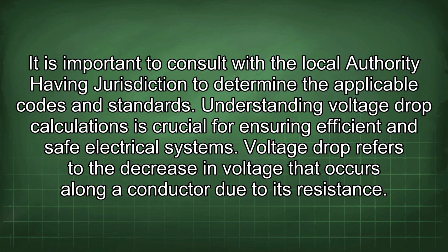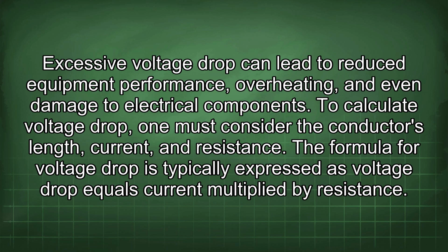Understanding voltage drop calculations is crucial for ensuring efficient and safe electrical systems. Voltage drop refers to the decrease in voltage that occurs along a conductor due to its resistance. Excessive voltage drop can lead to reduced equipment performance, overheating, and even damage to electrical components. To calculate voltage drop, one must consider the conductor's length, current, and resistance. The formula for voltage drop is typically expressed as voltage drop equals current multiplied by resistance.